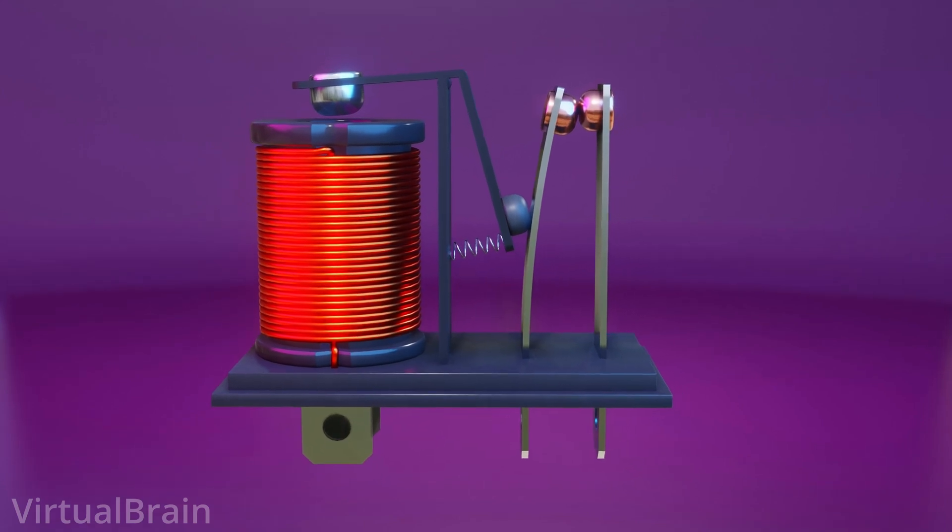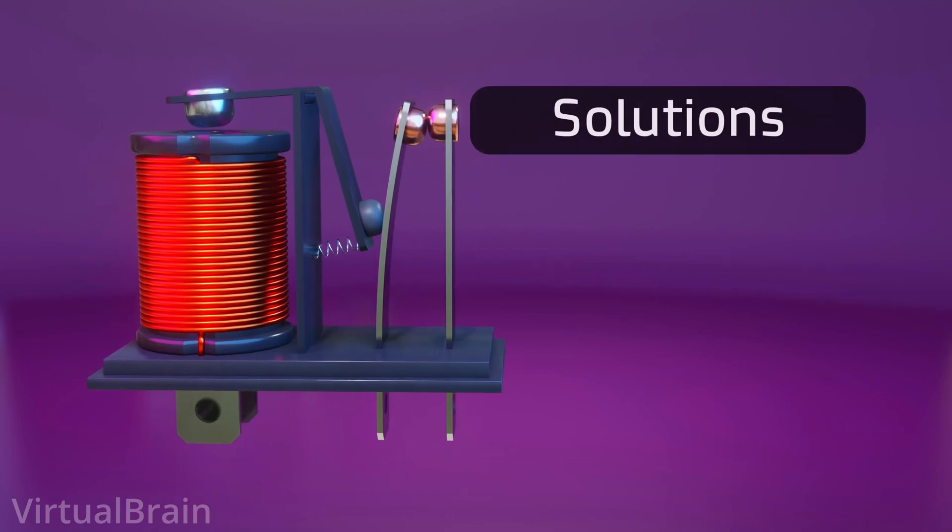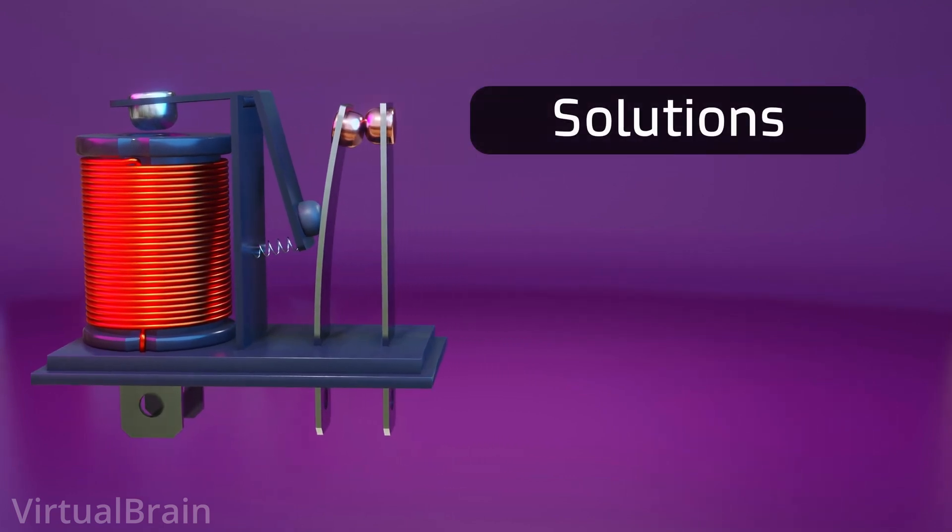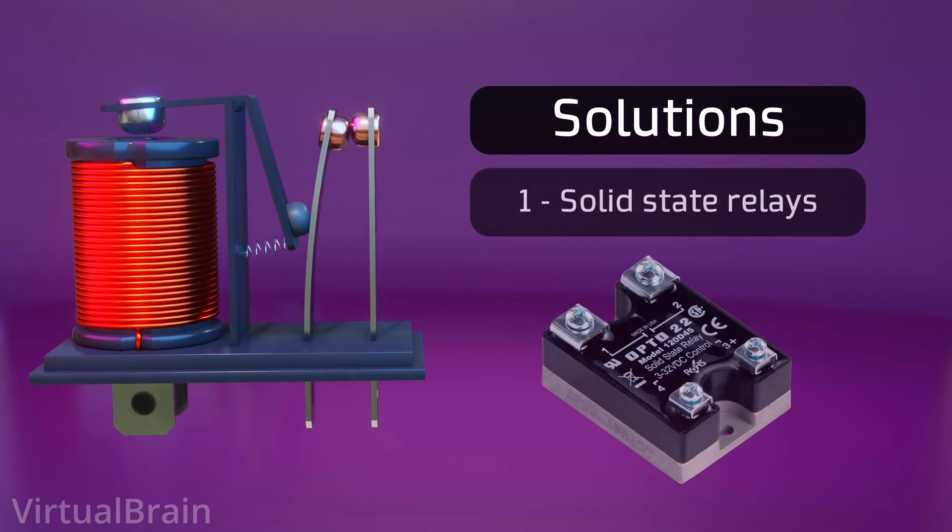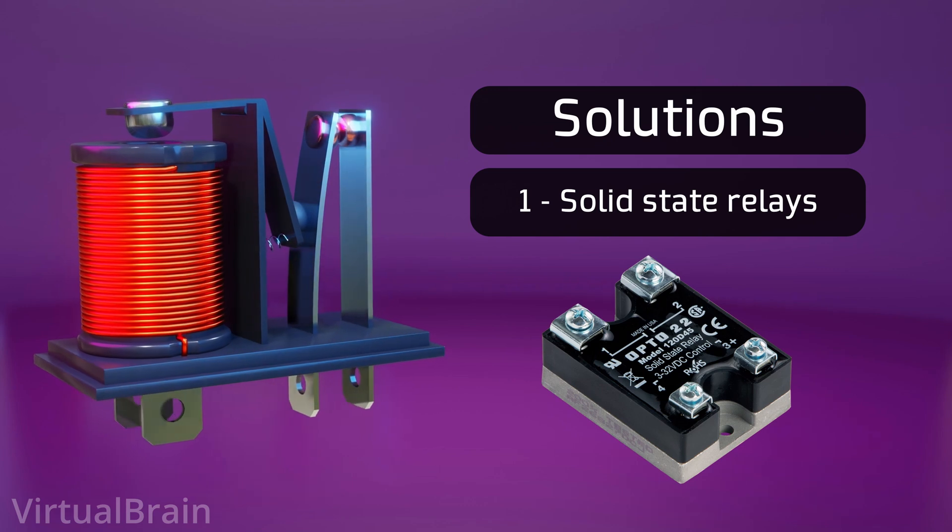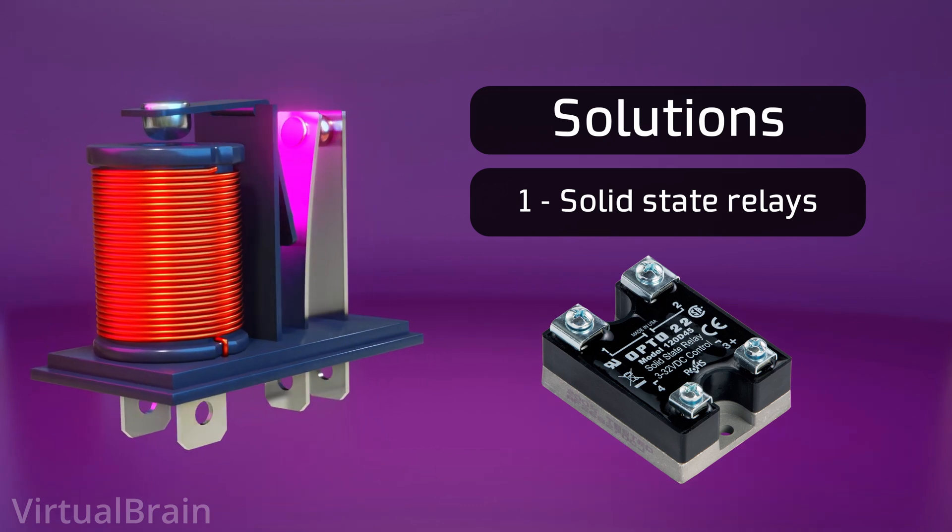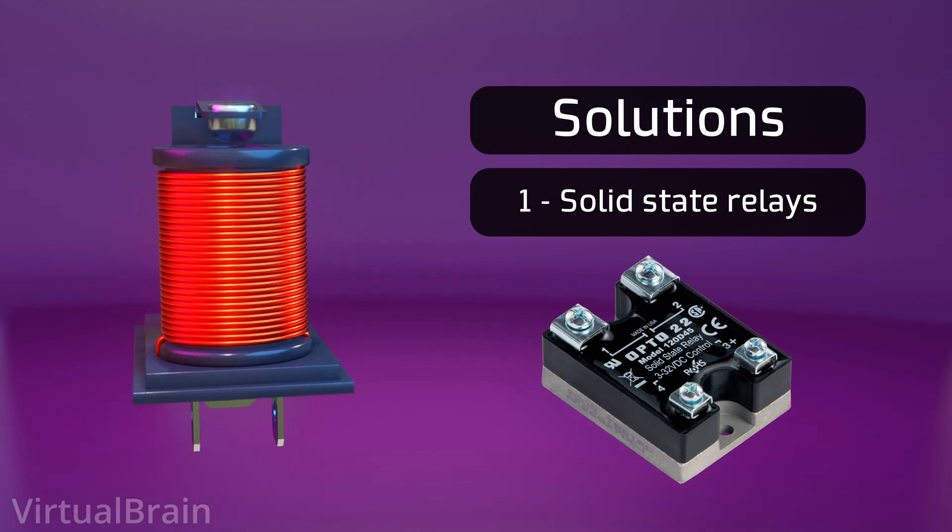For both cases, since the problem is directly related to the relay contacts which must physically move to open or close the circuit, the easiest solution would be to use solid state relays, which have no moving parts and therefore do not suffer from electric arc or the rebound effect. However, if we want to continue using electromagnetic relays, we also have some alternatives.